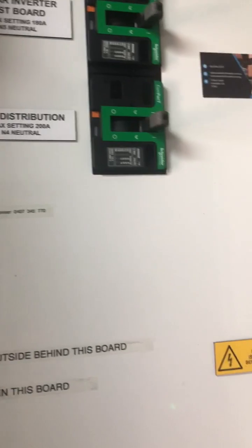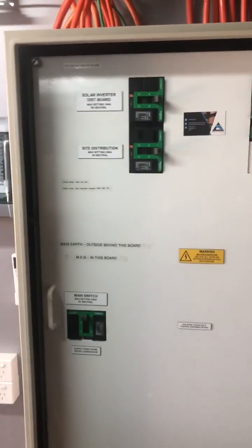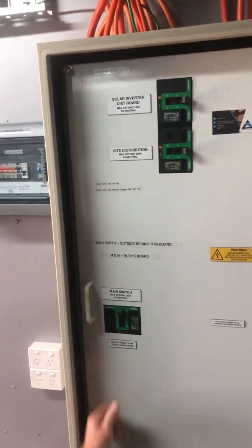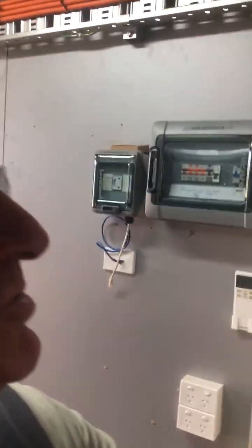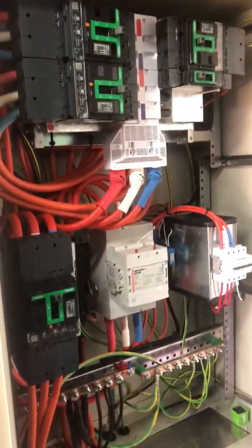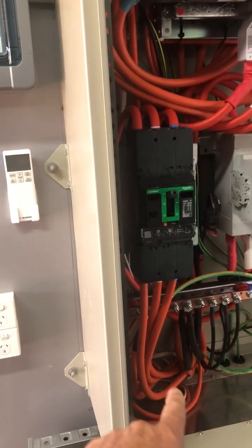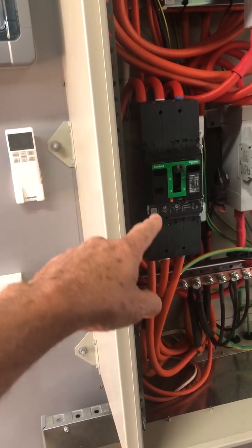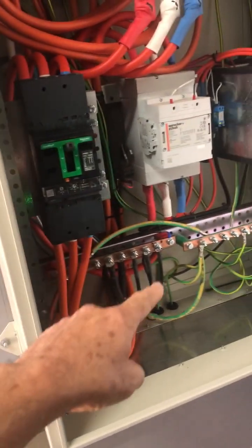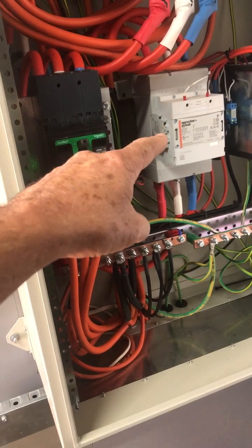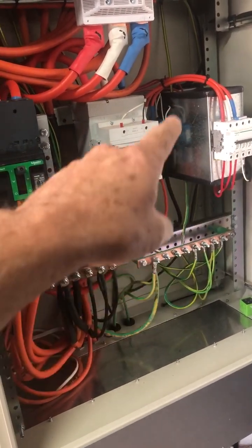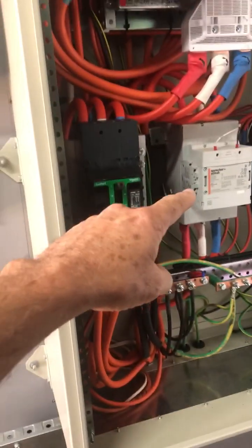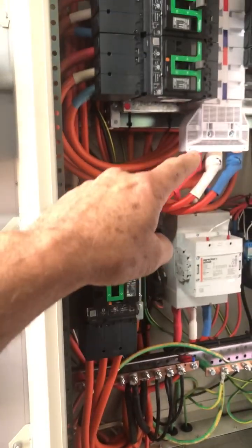Now inside this board, I'll just open it up for you. You've got to be very careful whenever you get into a switchboard. Okay, so now you'll see we have the cables coming from the generator, which come into this main switch here, out of the top of the main switch, and they come down through a circuit breaker here. Sorry, not a circuit breaker, a contactor. And there's other controls in here, but I won't get too deep into that. But this contactor always remains open, and the contactor is then connected to the bus bar up here, right? And everything's connected onto the bus bar.